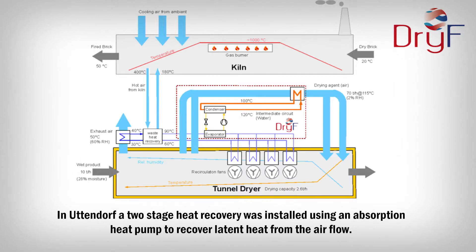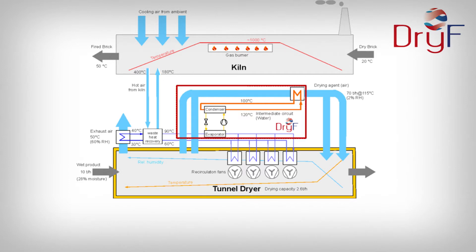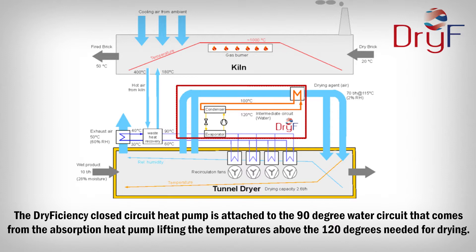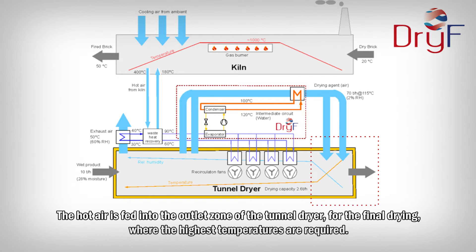In Uttendorf, a two-stage heat recovery was installed using an absorption heat pump to recover latent heat from the airflow. The DryFiciency heat pump, replacing a natural gas burner, is connected in order to supply the high temperatures that are needed for the drying of the bricks. The DryFiciency closed circuit heat pump is attached to the 90-degree water circuit that comes from the absorption heat pump, lifting the temperatures above the 120 degrees needed for drying. The hot air is fed into the outlet zone of the tunnel dryer for the final drying, where the highest temperatures are required.